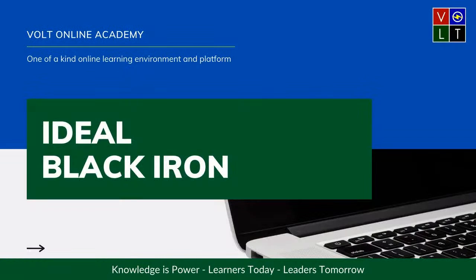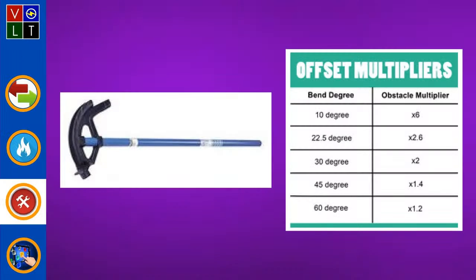All right. So, a really great tool review for me is the Ideal Black Iron, and I threw a few little box offset multipliers in here if you guys want to check them out. What we always use as electricians is the 30-degree multiplier, which is the ×2, and that's a common thing. Typically, you don't want to put a whole bunch of offsets in your pipe because you start adding degrees. And the job we're at right now, we can't exceed 270 degrees without doing a box.